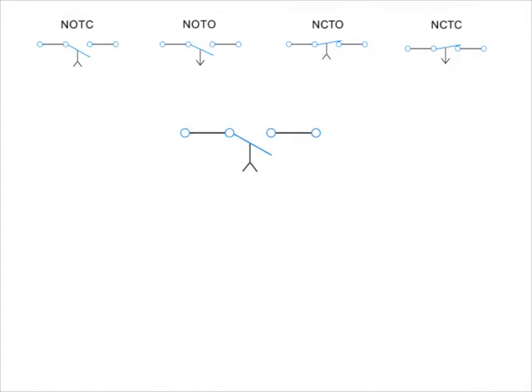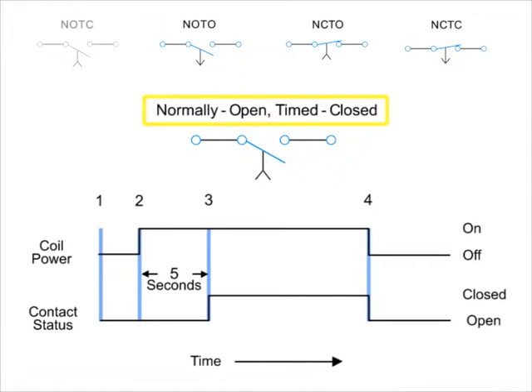First, we have the normally open, timed closed NOTC contact. This type of contact is normally open when the coil is unpowered or de-energized. After the coil has been continuously powered for a specified amount of time, in this example five seconds, the contact is closed. The contacts will immediately open when the coil is de-energized.